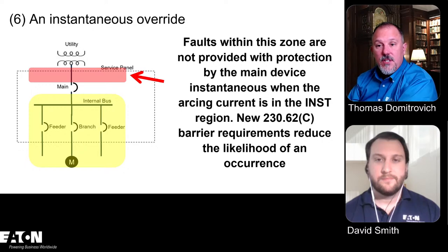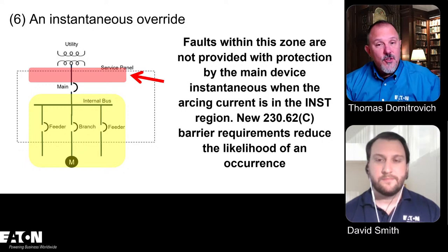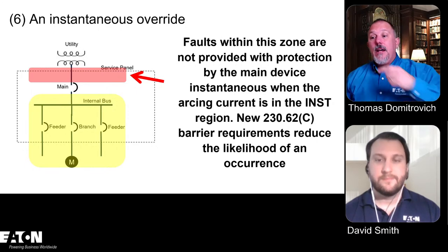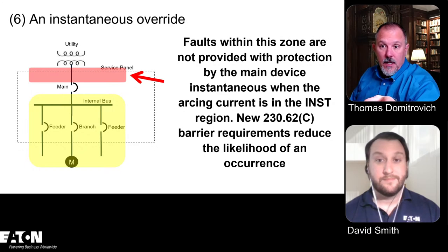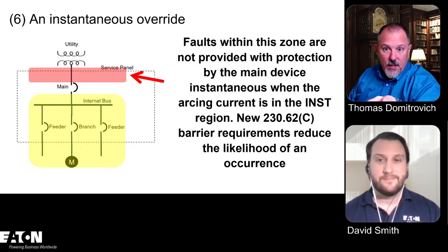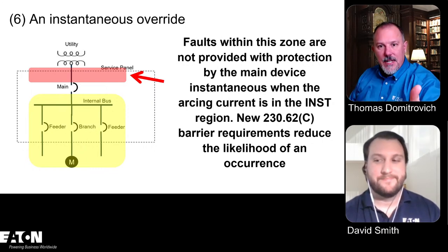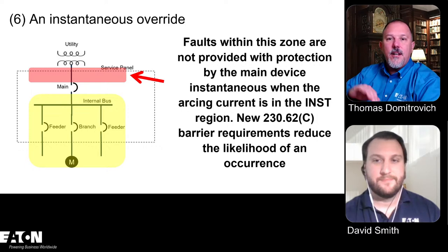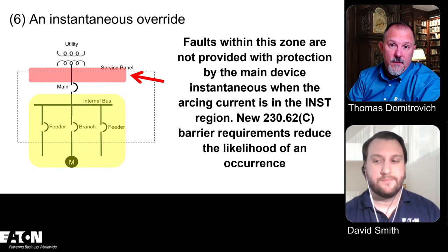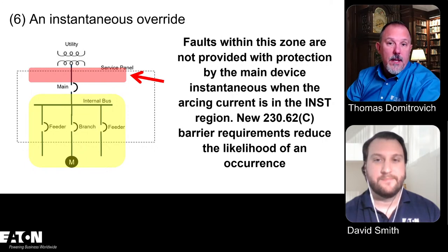Now, the 230.62(C) barrier requirements for service entrance equipment will help reduce the likelihood of the occurrence. What panel 10 just passed is that a panel on the secondary of a transformer will have to have a barrier on the main lugs. That was Jim Dollard's public input as well, because he recognizes, as do others, that when you have that main overcurrent protective device, you need to provide barriers to avoid unintended contact with those lugs. It's not going to prevent the line side propagation, but it will reduce the likelihood of it happening. As power systems people, that's our goal.